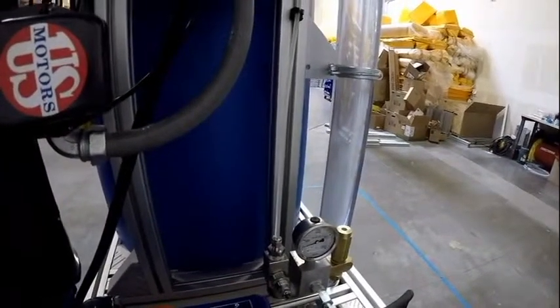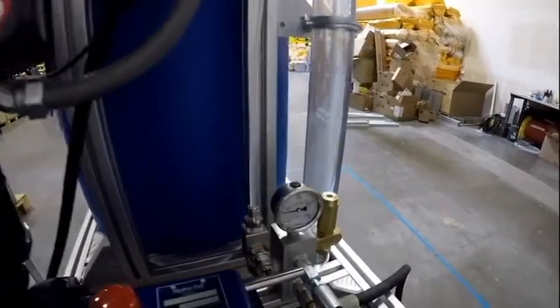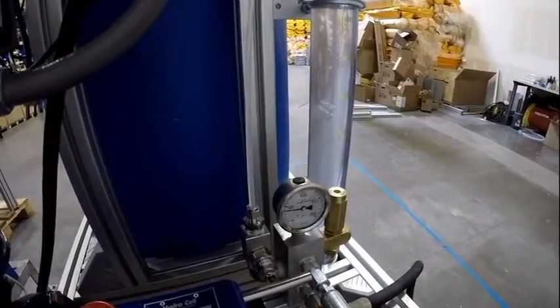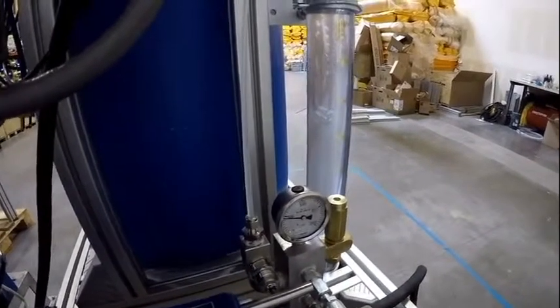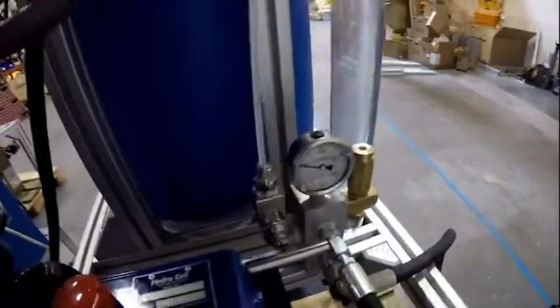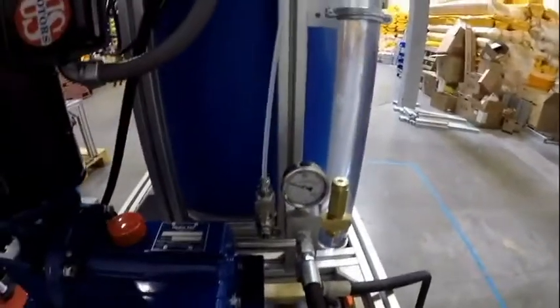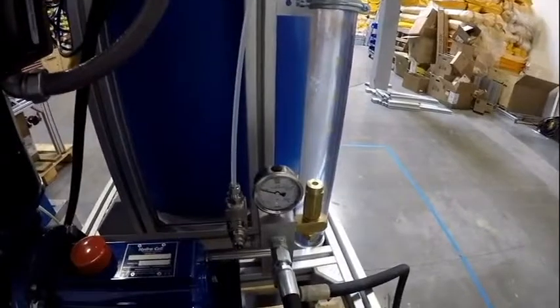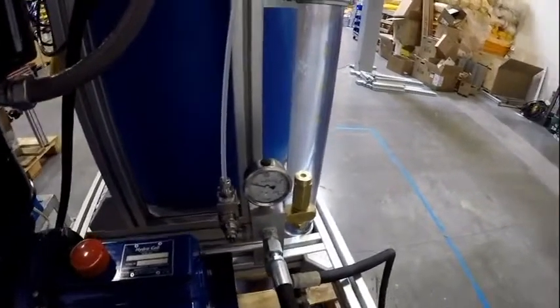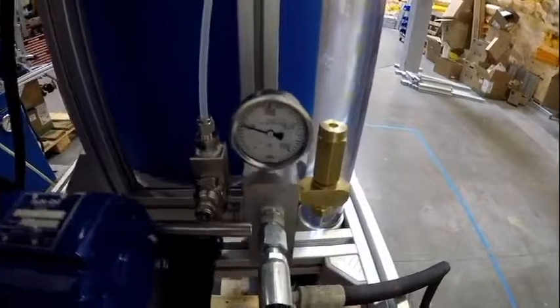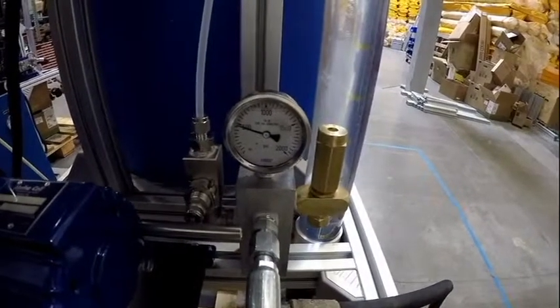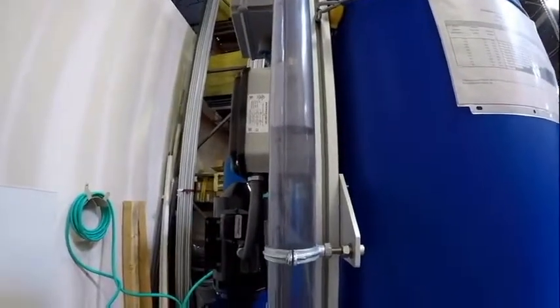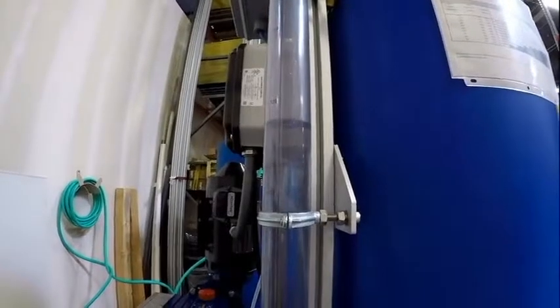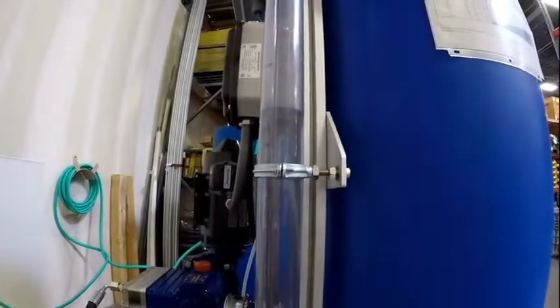Next, check your PSI gauge to make sure you're pumping under normal operating pressure. You can watch the PSI valve. Make sure it's right where it would be when you're normally running. We are then going to isolate the calibration tube by turning the valve so it's only pumping from the cal tube. You'll see the water start dropping in the tube after you turn the valve.